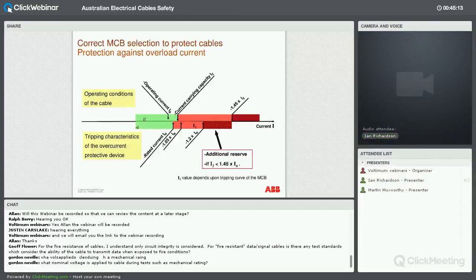On the lower line, we're looking at our protective device. So the first element, which we've got right here, is the rated current of our protective device, which is in the middle of our load current and the current carrying capacity of the cable. A couple of values here now of 1.05 and 1.2, depending on the characteristics of our breaker, and I've got some trip curves coming up. These values are quite important because that's the value where the breaker is likely to trip between those two in its thermal capacity. Then we also have this shaded area here, which is the additional reserve, again rated at 1.45 times this rated current. So the rated current being below the current carrying capacity, using our 1.45, we've got this extra reserve value here, but we should still be keeping below the ultimate limit of what the cable is going to be.